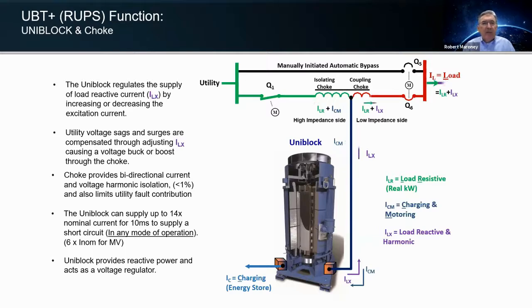Okay, as I said, the choke provides bidirectional current and voltage harmonic isolation. It'll take a 50% current harmonic or load harmonics and mitigate those and give you the isolation you need. You'll also notice, as I mentioned earlier, there are no filters on the input to the system. We don't need them because that choke provides that kind of filtration. Any questions about that?